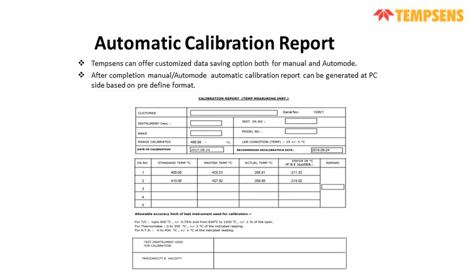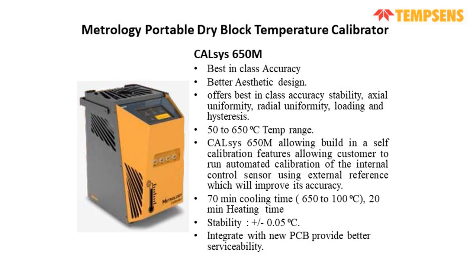So again, moving on to the metrology portable dry block calibrators. Metrology calibrators are best in class for accuracy. Then we have a very aesthetic design, and the temperature range for this 650M model is 50 to 650 degrees centigrade. It has a stability of plus minus 0.05 degrees centigrade, and it is integrated with a PCB. So it has good response and accuracy, and it has 70 minutes of cooling time, from 650 to 100 degrees, and it takes just 20 minutes to heat up to 650 degrees.